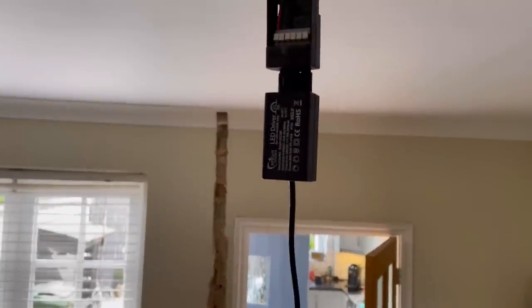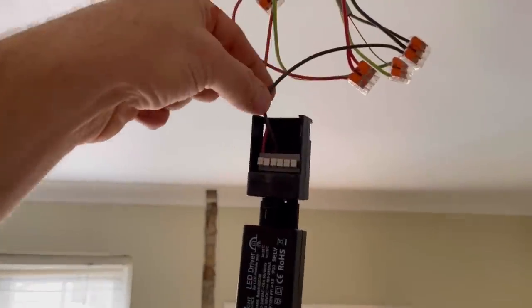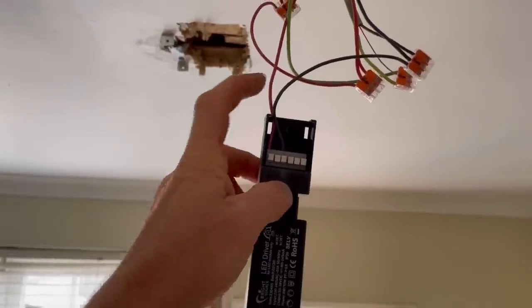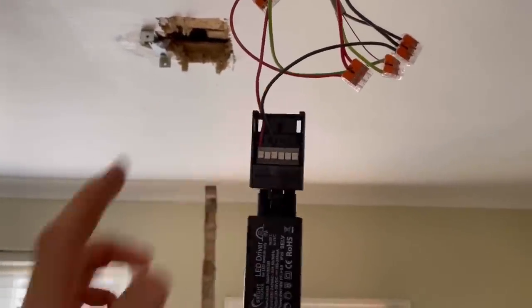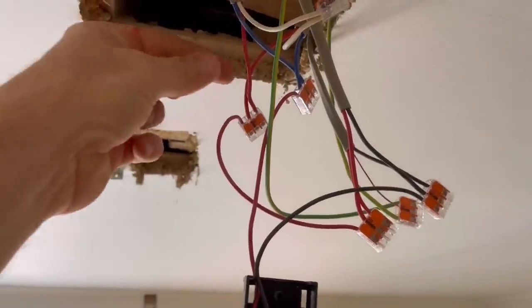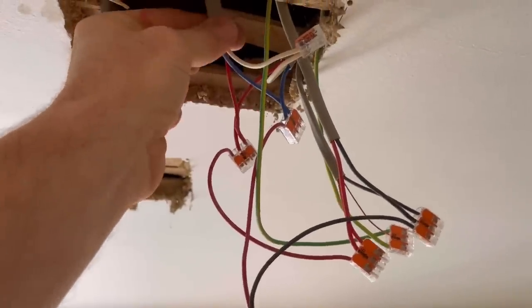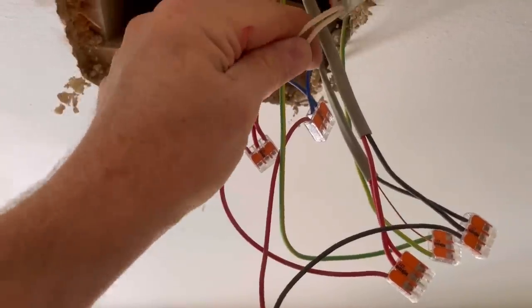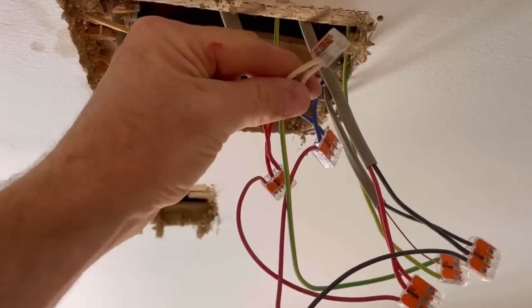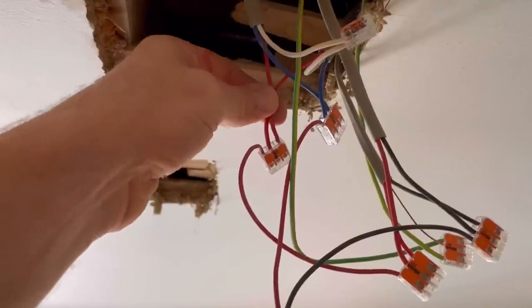I've just took a neutral straight to the light. Obviously there's no CPC, no earth at the moment, but this isn't obviously going to stay like this. Now we're going to look at the three-core cables for the two-way lighting. As said previously, the two white wires I've used as the commons.